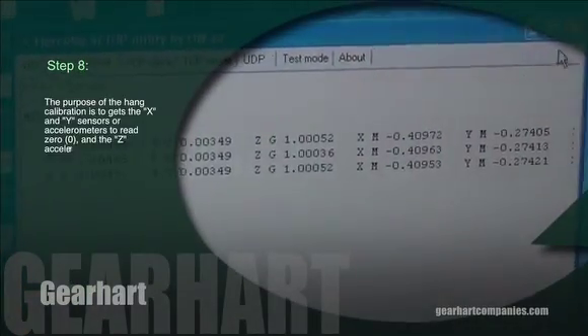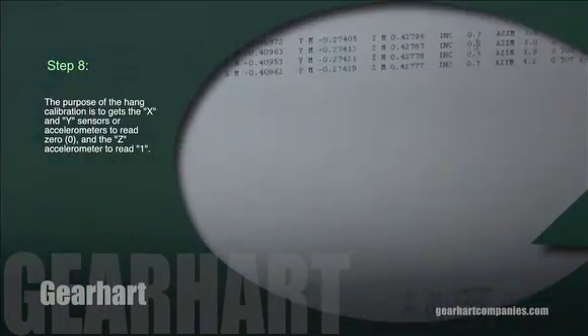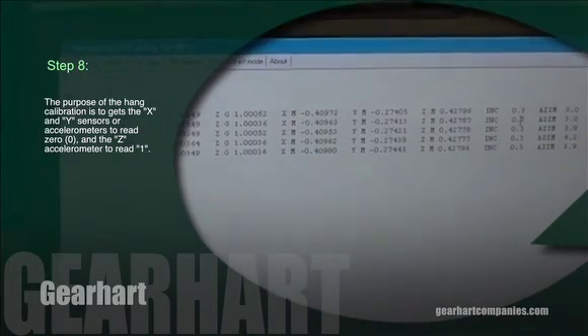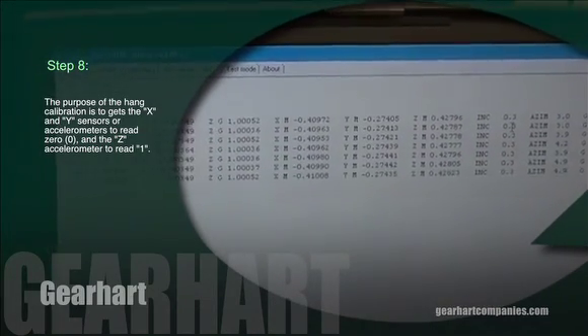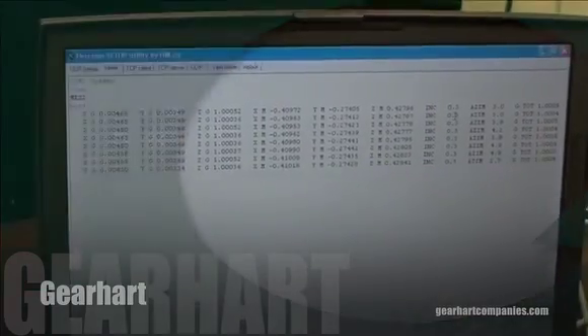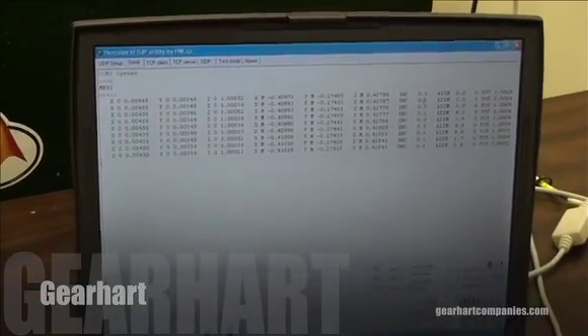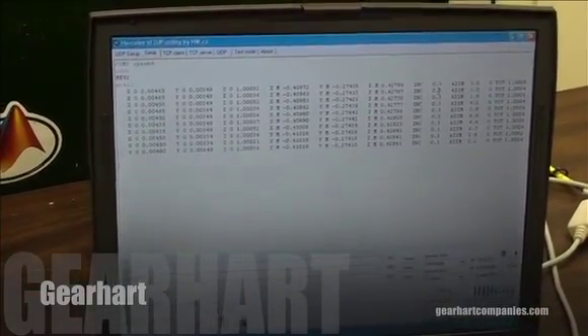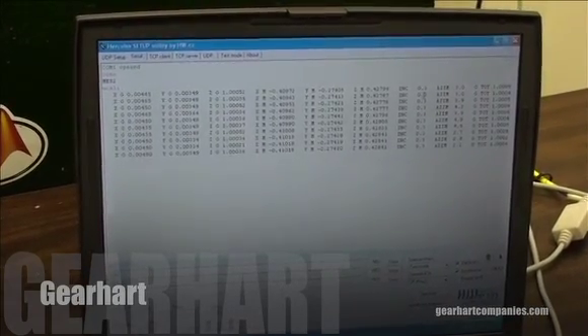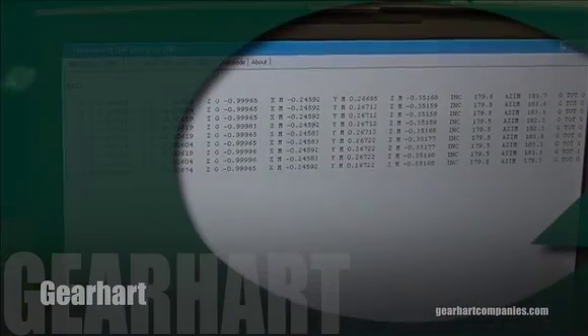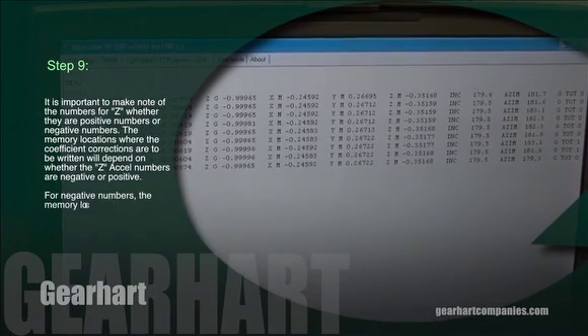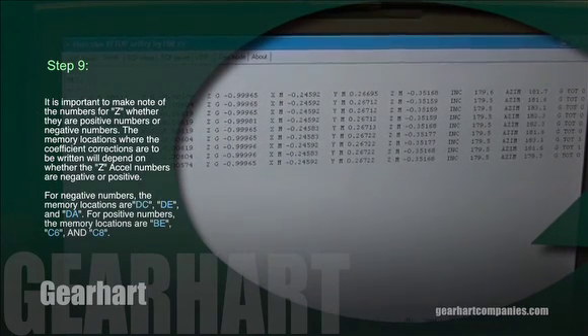Step 8. The purpose of the hang calibration is to get the X and Y sensors or accelerometers to read 0 and the Z accelerometer to read 1. Step 9. It is important to make note of the numbers for Z, whether they are positive or negative.